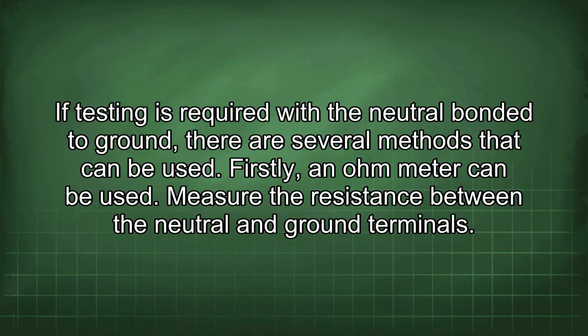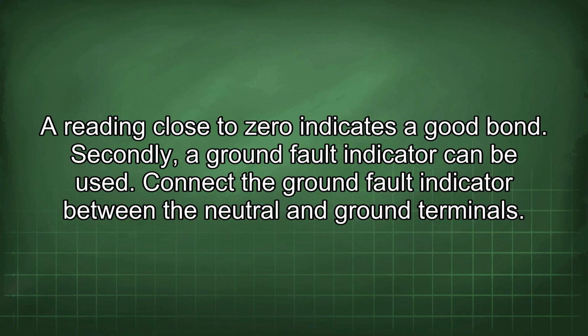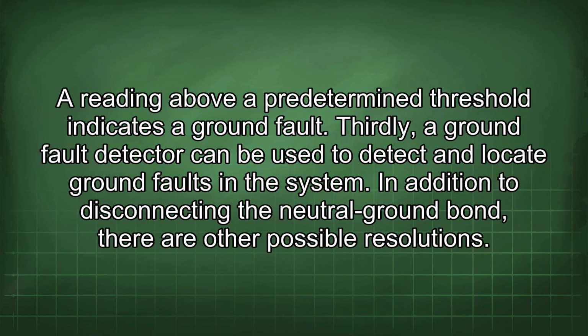Firstly, an ohm meter can be used. Measure the resistance between the neutral and ground terminals. A reading close to zero indicates a good bond. Secondly, a ground fault indicator can be used. Connect the ground fault indicator between the neutral and ground terminals. A reading above a predetermined threshold indicates a ground fault. Thirdly, a ground fault detector can be used to detect and locate ground faults in the system.